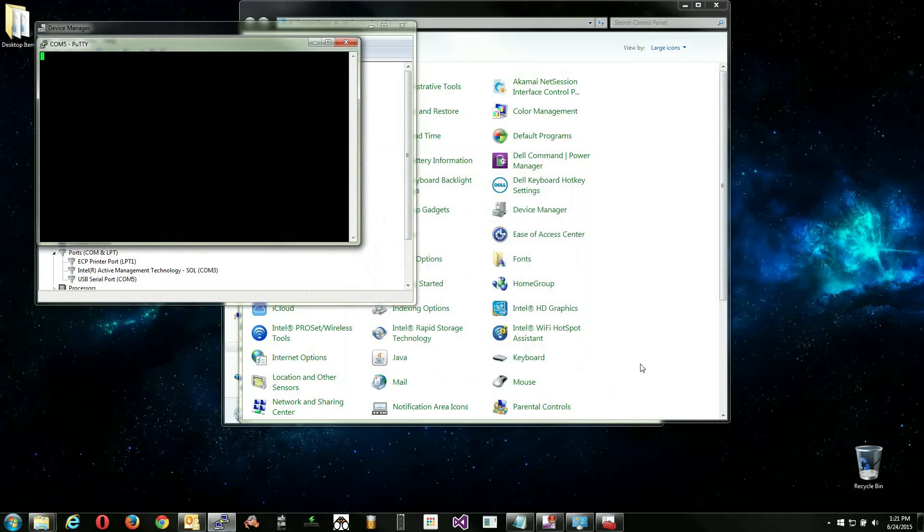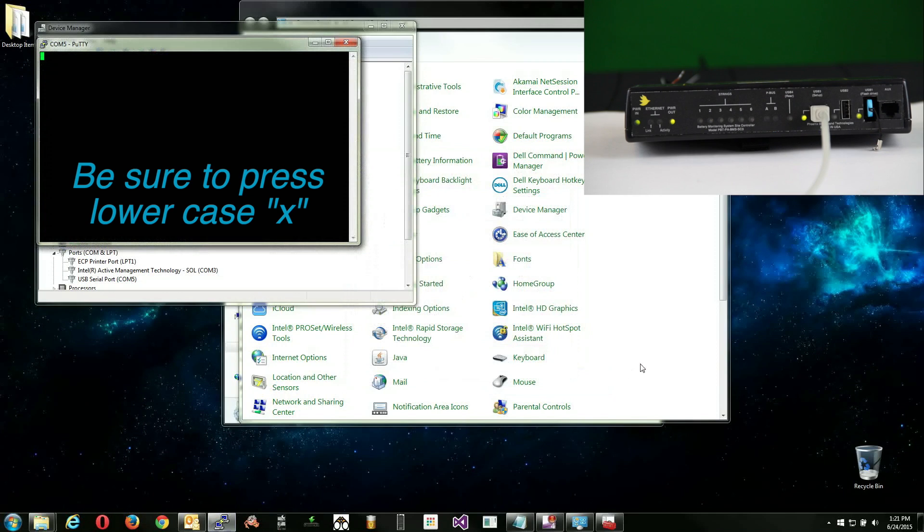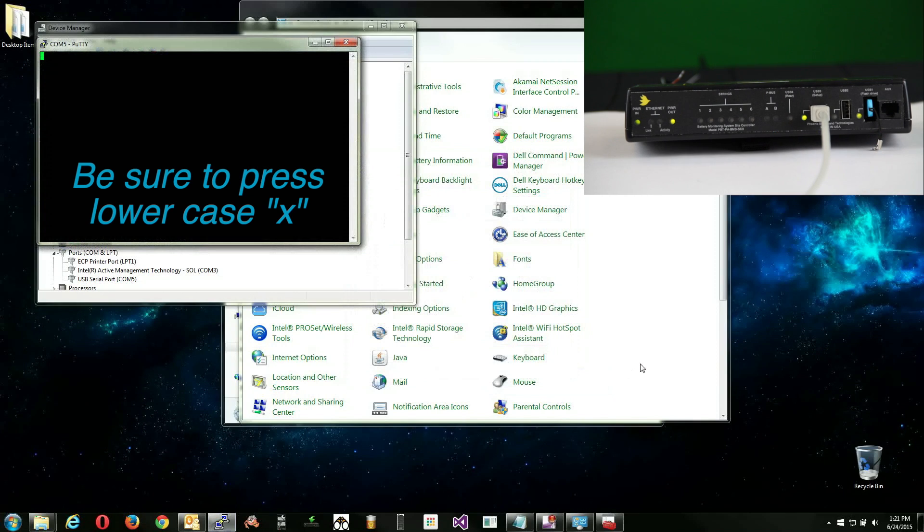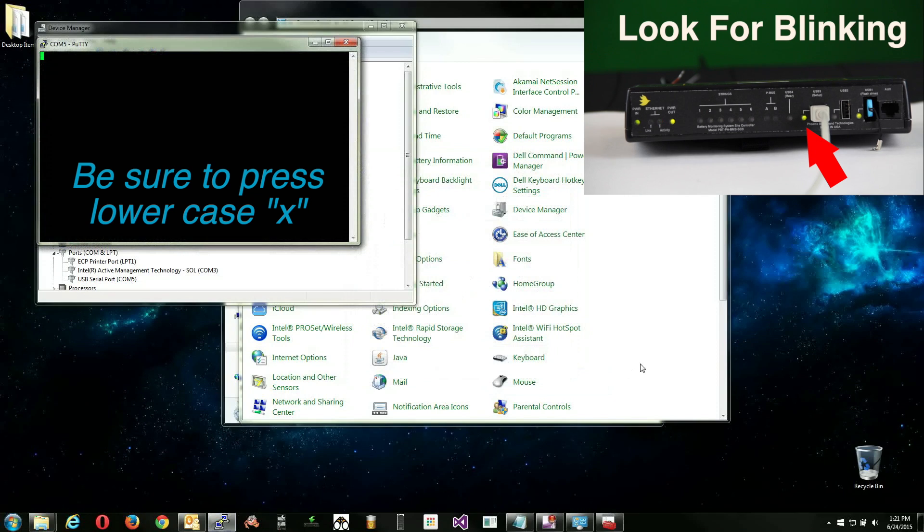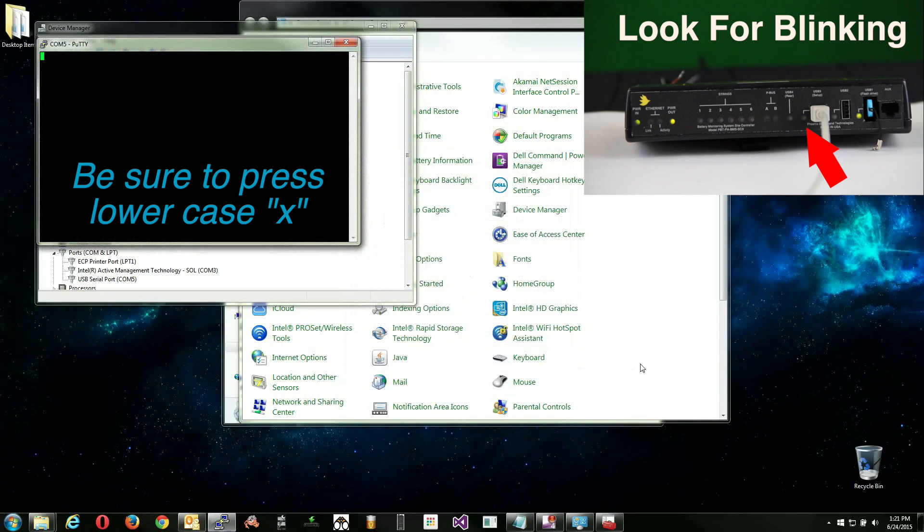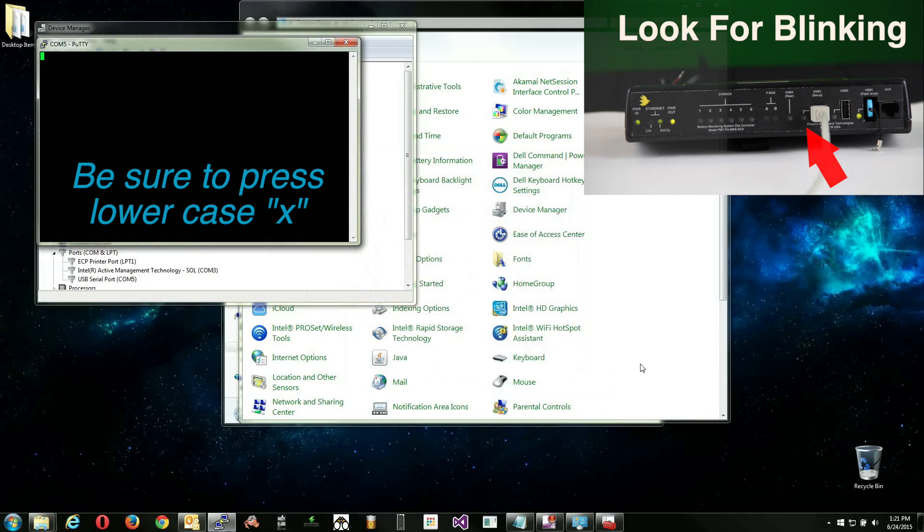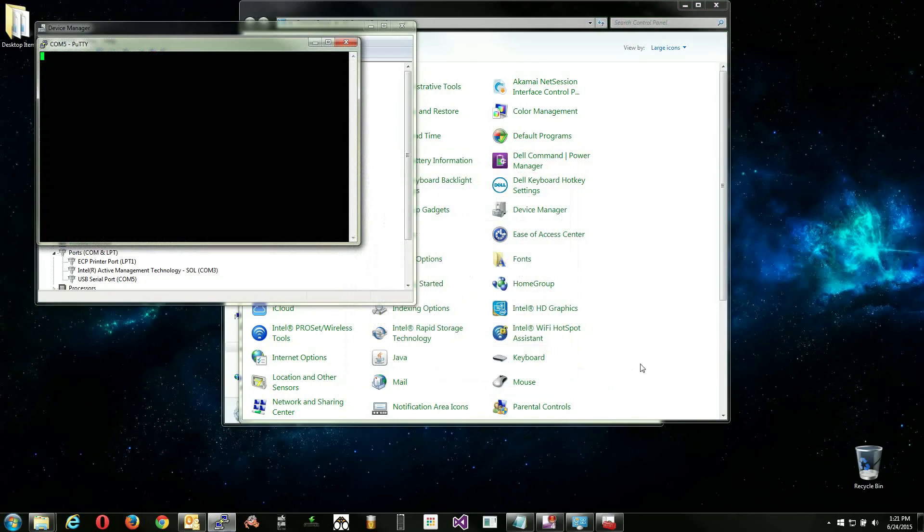You will immediately be shown a blank screen. From here, you will need to press and hold down the X key on your keyboard. This reboots the site controller so that you can access it via serial connection. While you are holding down the X key, you should see the LED next to the USB input on the site controller blinking. This blinking indicates that the site controller acknowledges that you are holding down the X key. If you do not see this LED blinking, you may want to repeat this process. You can always contact PBT for additional support.